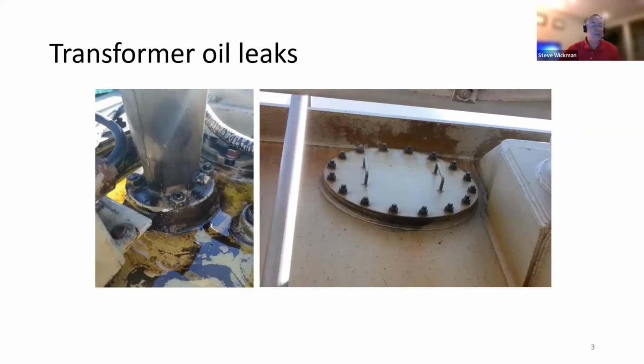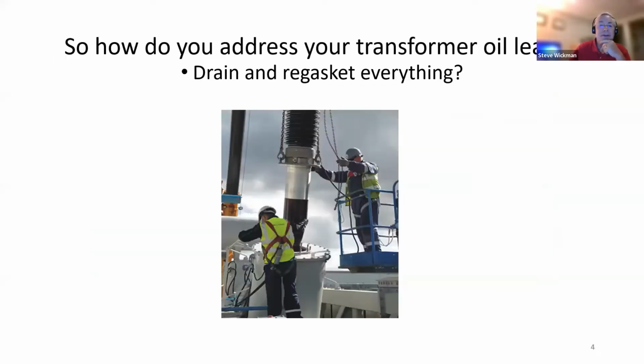Customers made an attempt with some sort of external epoxy, and with the puddles around this thing, it's pretty apparent that the fixes didn't work very well. In addition, these access hatches that are in various places on transformers are 99% of the time below the level of the oil in the unit, so it makes it a bit of an involved chore to replace gaskets on those without draining the entire transformer. So how do you address your transformer leaks?